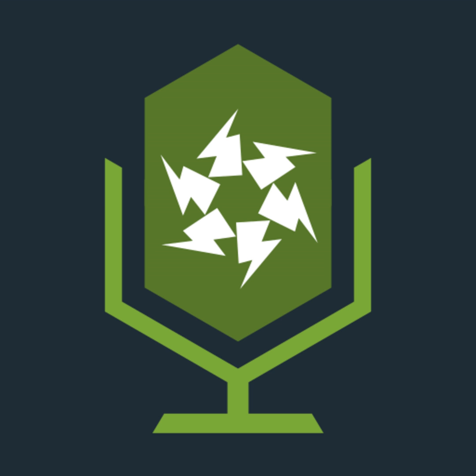Just to talk about protective conductors again here in general, we've got the means of earth there. That's the main earthing terminal, so that's the earthing conductor. We have an extraneous conductive part. We have another extraneous conductive part. And so the main protective bonding conductor goes from the main earthing terminal to the extraneous conductive parts. We then have current using equipment here and here. So this conductor is the CPC, circuit protective conductor.